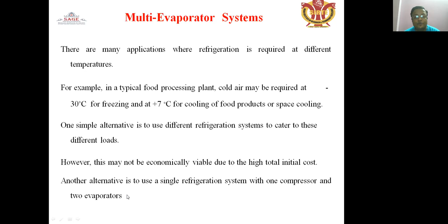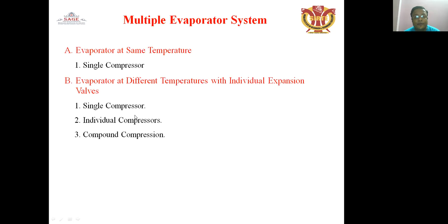One simple alternative is to use different refrigeration systems to cater to these different loads. However, this may not be economically viable due to the high total initial cost. Another alternative is to use a single refrigeration system with one compressor and two evaporators. In a multiple evaporator system, when the evaporators are at the same temperature, a single compressor is used, which is a simple system. For evaporators at different temperatures with individual expansion valves, you can use a single compressor, individual compressors, or a compound compressor, which helps improve the refrigeration effect.